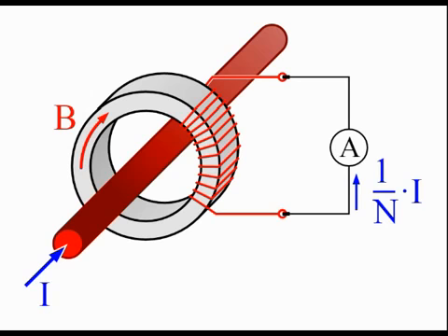Shapes and sizes can vary depending on the end user or switchgear manufacturer. Low voltage single ratio metering current transformers are either a ring type or plastic molded case. Split core current transformers either have a two-part core or a core with a removable section. This allows the transformer to be placed around a conductor with a minimum disturbance. Split core current transformers are typically used in low current measuring instruments, often portable, battery operated, and handheld.